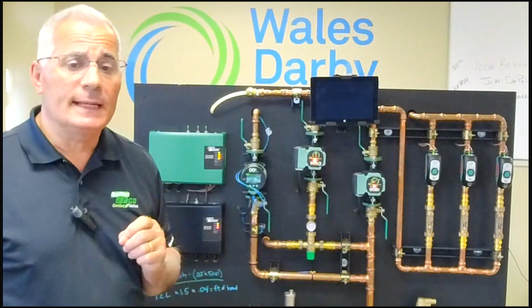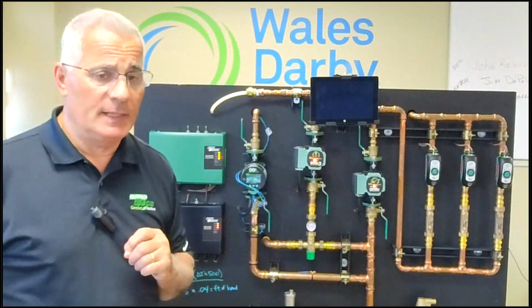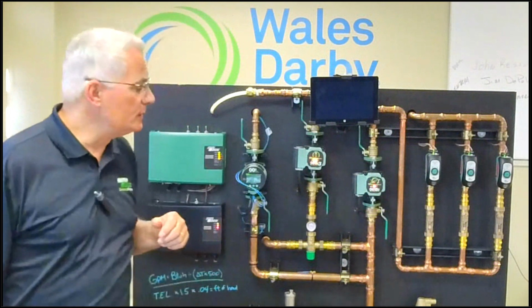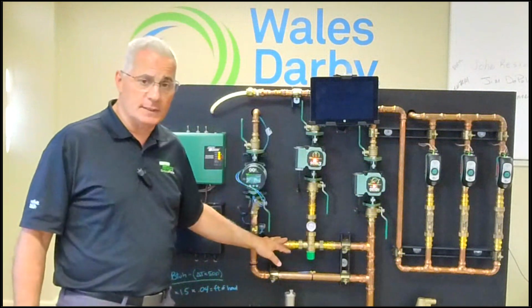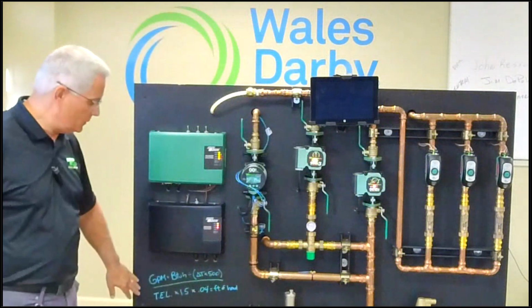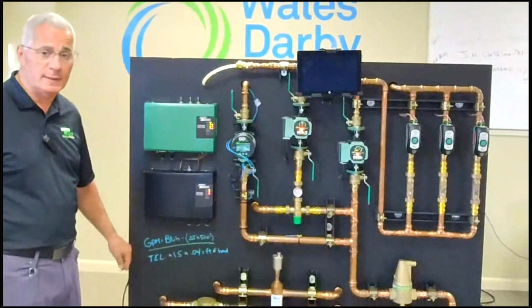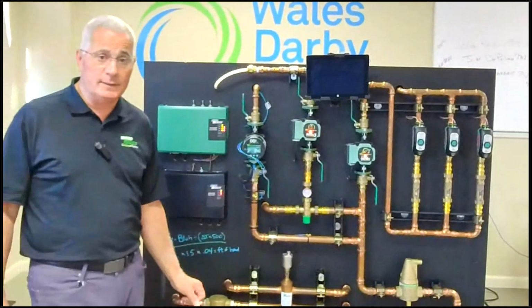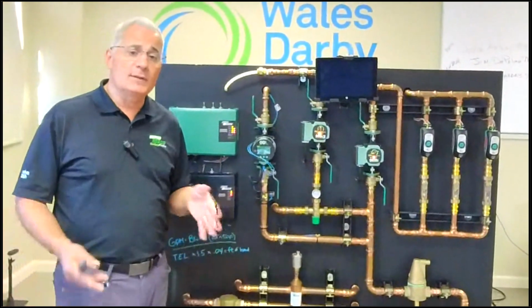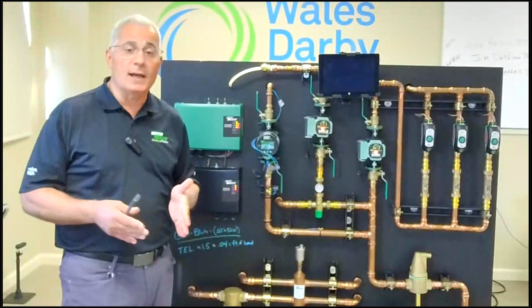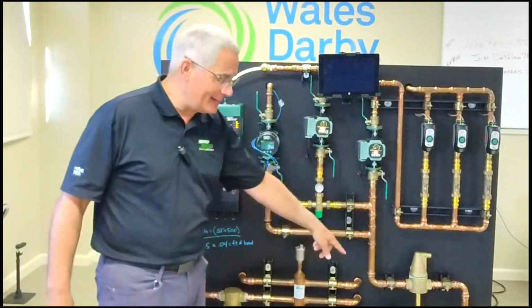Again, your download today was the Taco catalog. Page 57 will show you the different pipe sizes based on GPM. It will show you the universal hydronics formula. It will show you the head loss formula that is in there. It'll also have a conversion chart of PSI to head. We have that written down here on the bottom.